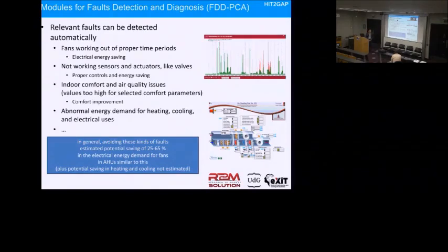And we can say that here the air handling units are well operated, so the faults recognized here are not a lot. But in general, we developed some scenarios to estimate this value of saving that can be reached in other situations. Considering, for example, that for 1 week in a year, a sensor can be broken.